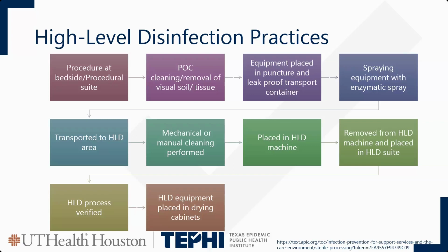So the first thing that you'll do while you're in the room, donned appropriately in the proper scrubs and PPE, is see the visual cleaning, or removal of visible tissue or fluids, from that device. That will be with a sterile sponge or a lint-free cloth from the stem of it all the way down to the device, and it should be one motion, one direction. So you want to remove the physical tissue or blood from that device and then see it being placed in a puncture- and leak-proof transportation container, and the keywords for that are puncture and leak-proof. Once it's placed in the container, you want to spray it with your enzymatic spray, which helps decrease the bioburden and prevents biofilm from forming, to make it easier to clean. So you want to see it sprayed, and at that point, that enzymatic spray should keep that device completely wet until it's processed.